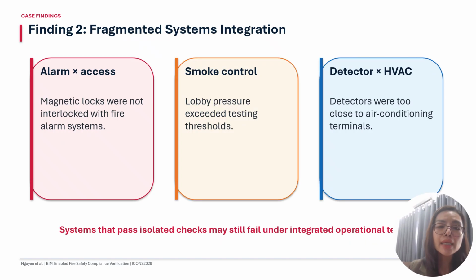Finding two is fragmented systems integration. In alarms and access, the magnetic locks were not interlocked with the fire alarm system. In smoke control, lobby pressure exceeded testing thresholds. In detector and HVAC, the detector was too close to air conditioning terminals. So a system that passed isolated checks may still fail under integrated operational testing.